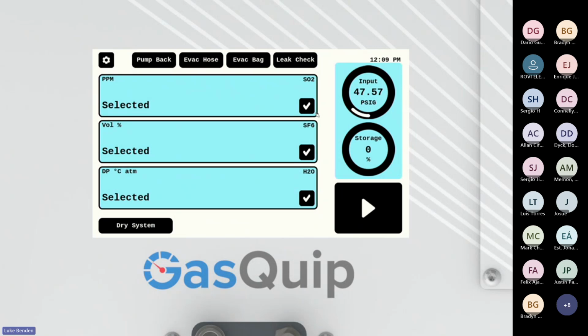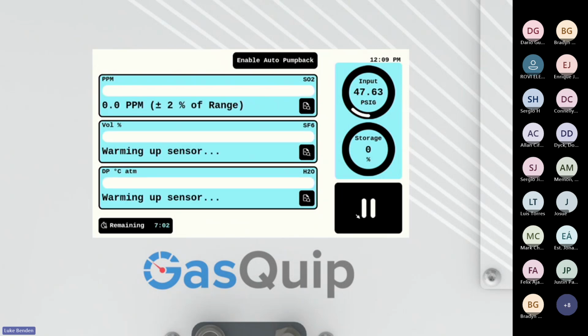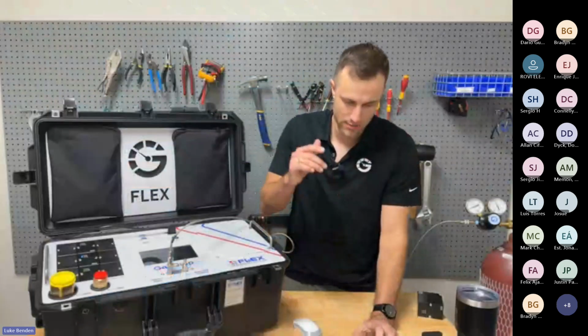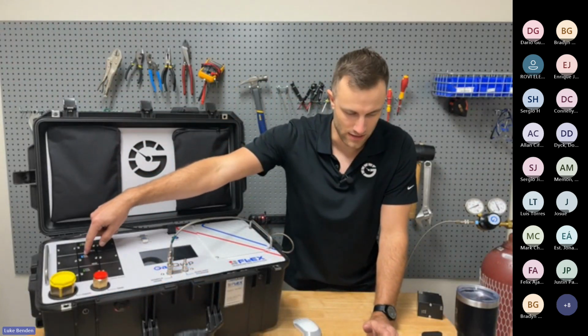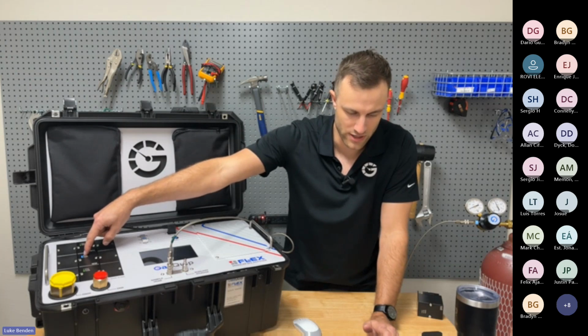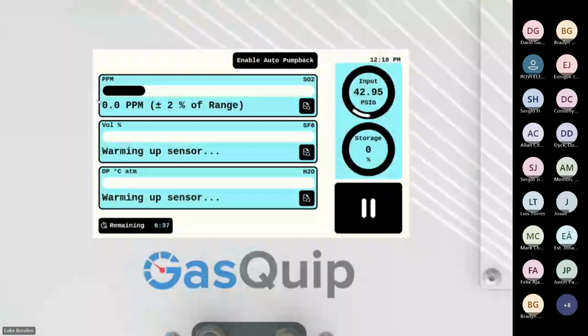We've got gas running through the line, everything's set up. We've selected all of the sensor modules that we need to run, and all we do is press play. So we'll have a live readout of the value that the sensor is currently measuring. And I can show you on the analyzer itself, might be kind of hard to see, but there are lights that light up as the sensor module is running to tell you that it's currently running as well. So you have the live readout.